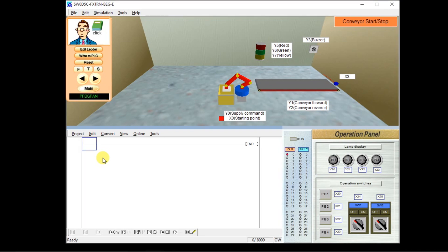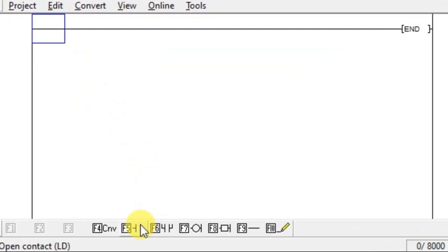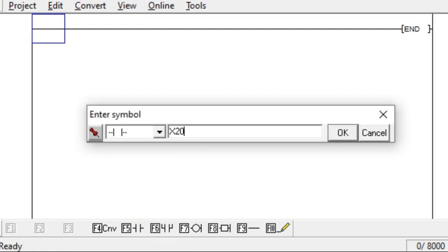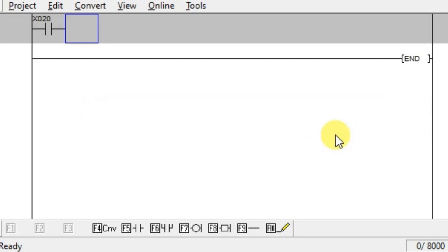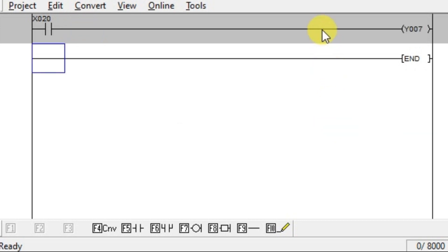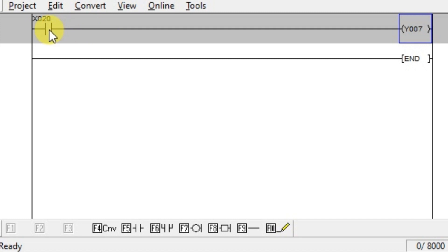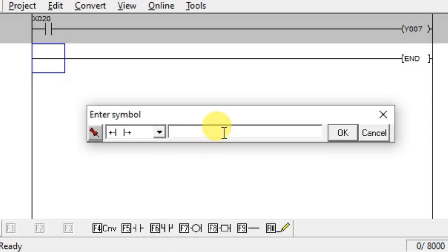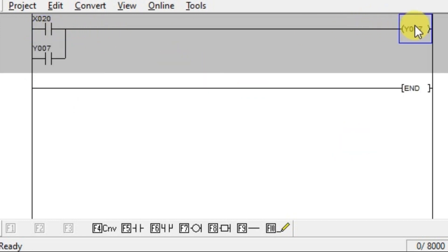Go to the logic. We need one input push button, which is x20. Take one NO contact and enter x20. We need to turn on the yellow lamp and buzzer, so take an output coil instruction and enter the yellow lamp address y7. We have to latch the yellow lamp because it must turn on for 10 seconds. The input x20 is a push button — it gives only one single pulse. So to keep the output on, take one branch with NO contact and enter the output address y7. When the input is activated, the output turns on, and due to the latch, the output stays ON even though the input is removed.